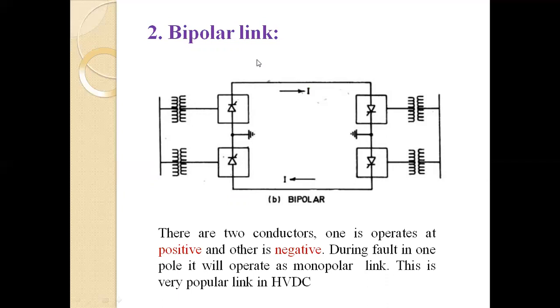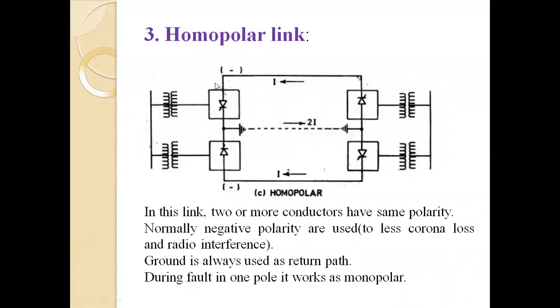So in the bipolar link, there are two conductors. One conductor is on the upper side and the second conductor is on the lower side. One operates at positive and the other at negative. So if this conductor is positive polarity, then this conductor is negative polarity. During a fault, if one pole fails, the link will operate as a monopolar link. This is very popular, because at the time of a conductor breakdown we can continue by using it as a monopolar link. So this bipolar link is very popular in the HVDC system.